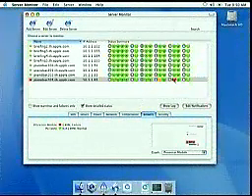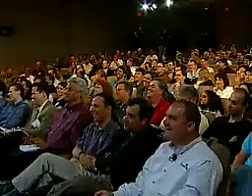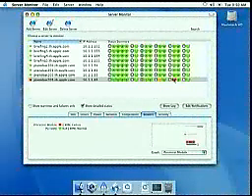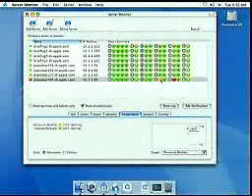Surprise. So the red warning tells us that fan number 1 has stopped working. You can see it's not spinning at all. So we now know a fan's gone down. Well, guess what the yellow warning is? The yellow warning is it's getting warm there in the processor module because the fan's gone down. It's not critical yet, but I have time to do something before it does become critical.